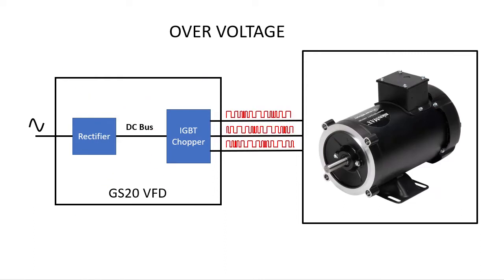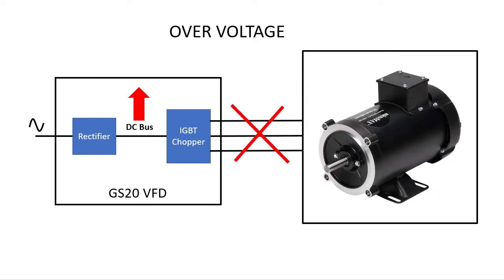The good news is the GS20 drives have several ways to deal with that. In the extreme case where the deceleration rate is raising the DC bus too fast for the drive to manage, the drive says I can't handle that and it shuts down its outputs, displays the overvoltage fault and leaves the motor to spin down by itself, which in my little test rack can take several minutes.